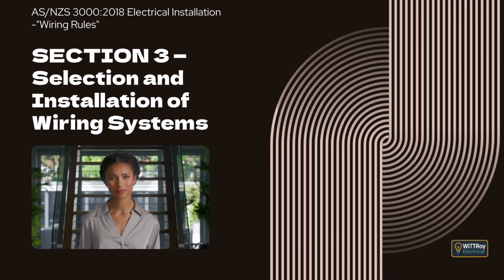Clause 3.12.4 Distance between supports. This clause explains that the span length between supports for aerial conductors must not exceed the maximum values specified for the conductor type and size. Longer spans may be used only where the design follows sound engineering practice. This clause recognizes that correct span length helps control sag, tension, and mechanical stress on the conductors.